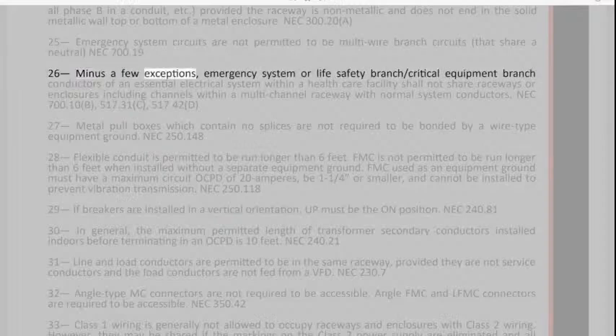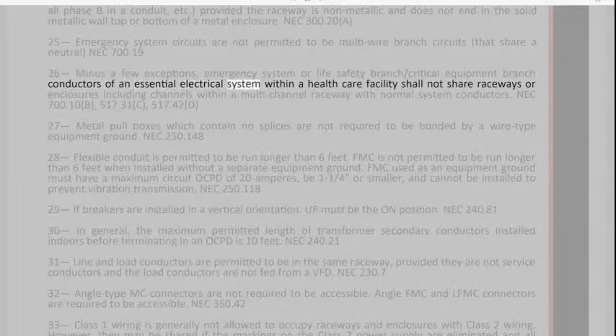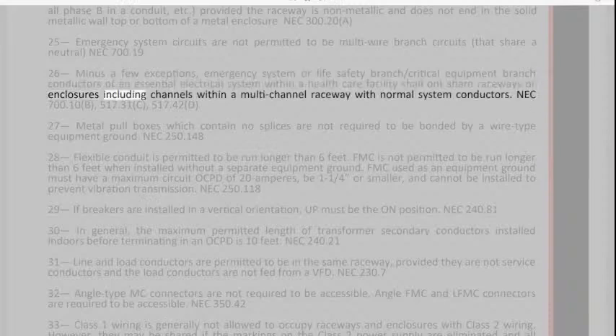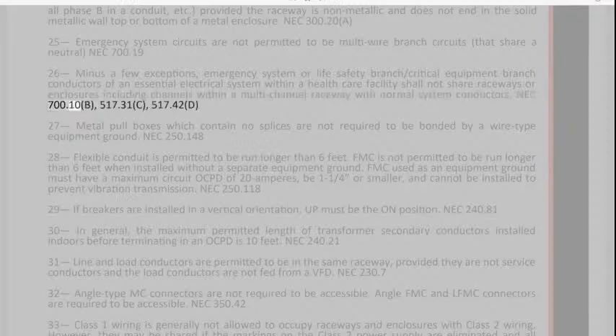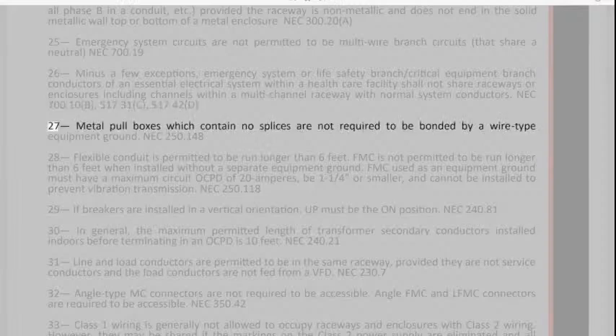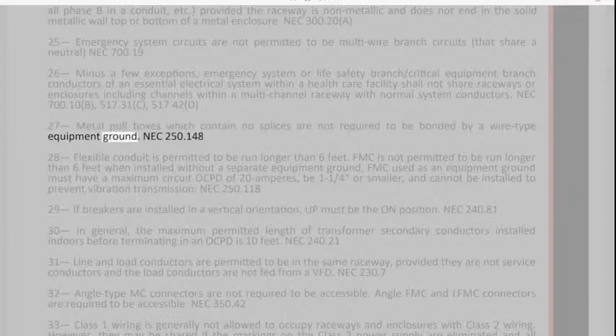26. Minus a few exceptions, emergency system or life safety branch/critical equipment branch conductors of an essential electrical system within a healthcare facility shall not share raceways or enclosures, including channels within a multi-channel raceway, with normal system conductors. NEC 700.10, B, 517.31, C, 517.42, D. 27. Metal pull boxes which contain no splices are not required to be bonded by a wire-type equipment ground.